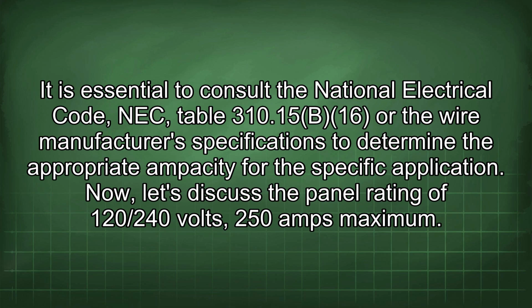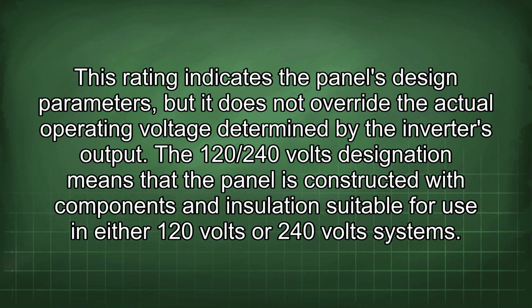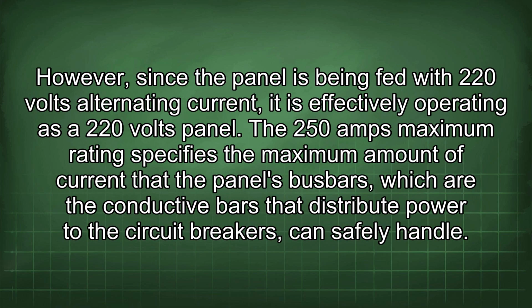Now, let's discuss the panel rating of 120/240 volts, 250 amps maximum. This rating indicates the panel's design parameters, but it does not override the actual operating voltage determined by the inverter's output. The 120/240 volts designation means that the panel is constructed with components and insulation suitable for use in either 120 volt or 240 volt systems. However, since the panel is being fed with 220 volts alternating current, it is effectively operating as a 220 volt panel.